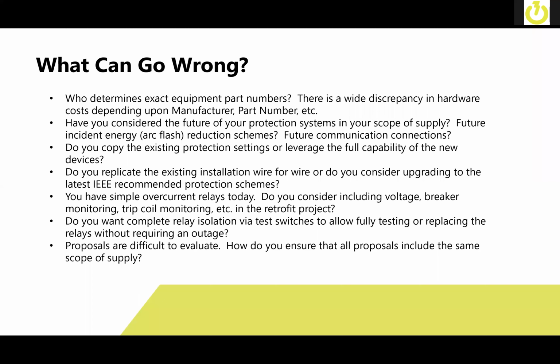Do you want to replicate the existing installation wire for wire, or do you want to consider upgrading to the latest IEEE recommended protection schemes? Protection schemes have changed since some of these plants were built, especially if they were built back in the 50s and 60s. IEEE has looked at all the different deficiencies in the systems, and they come up with new recommendations.